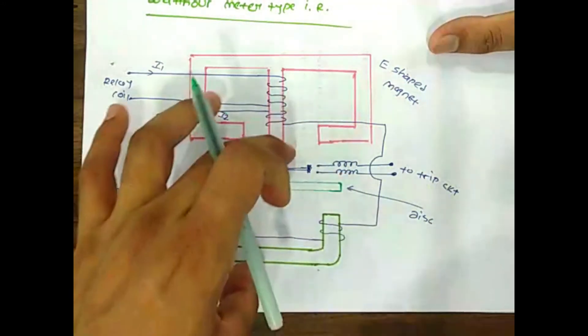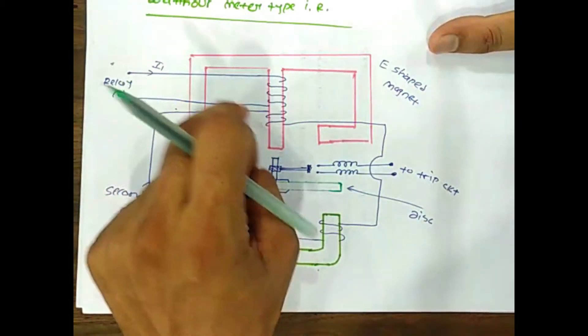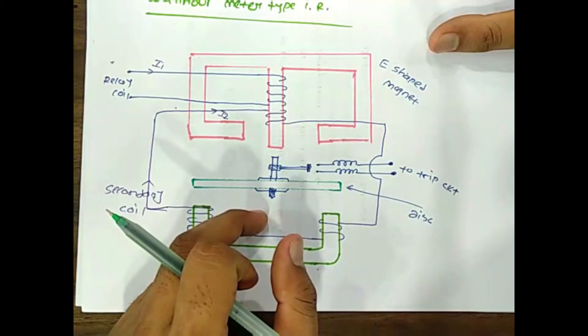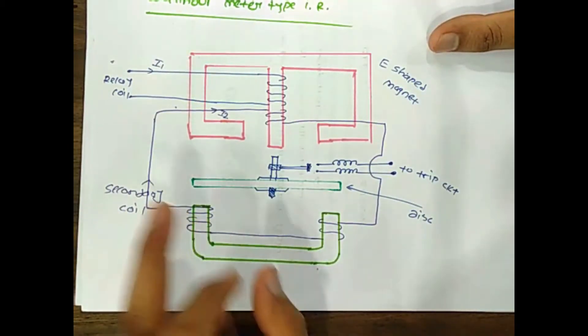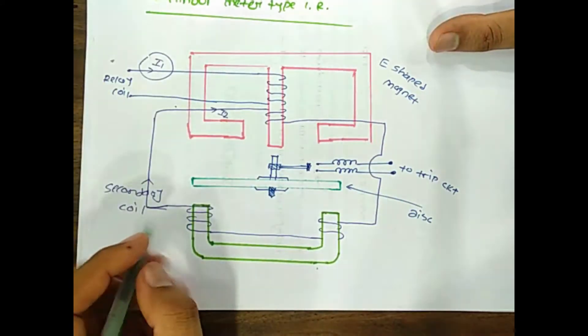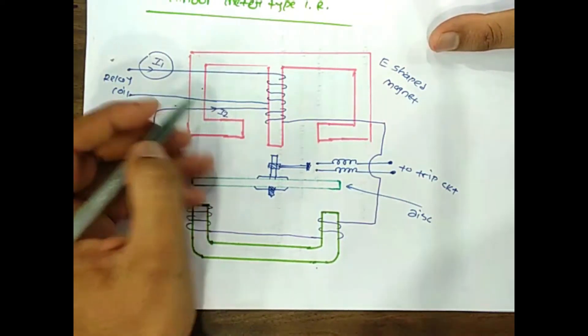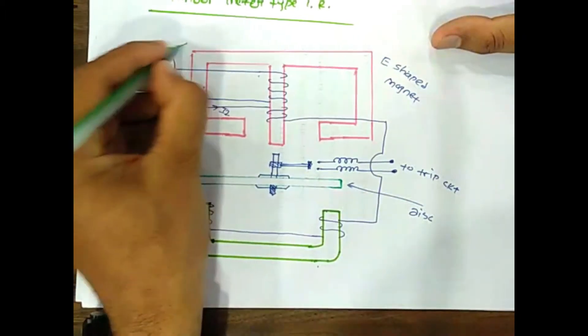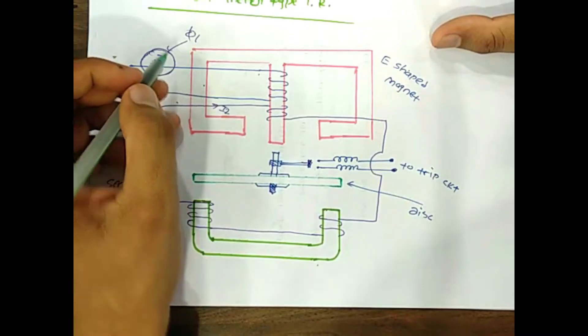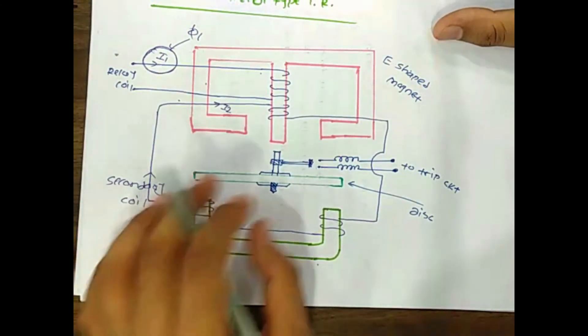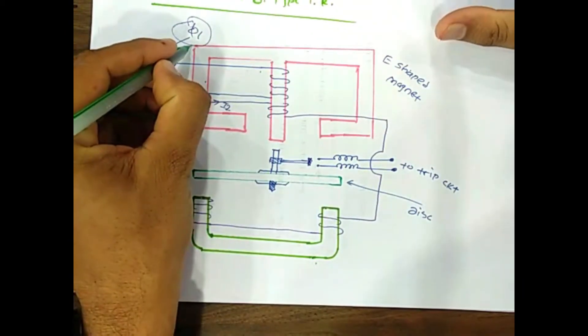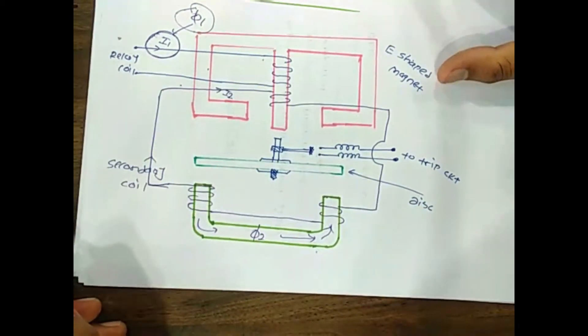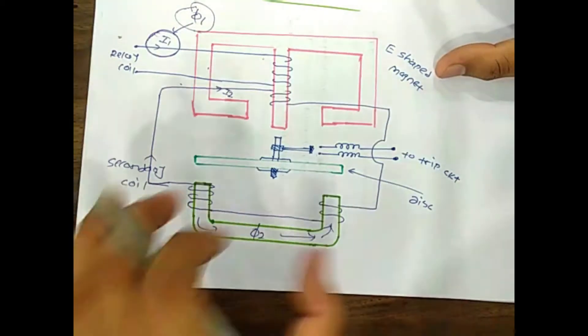The upper E-shaped magnet carries both the primary winding and secondary winding. The primary winding is the relay coil and the secondary winding is wound separately. The primary carries the relay current i1, which produces the flux phi1 in this particular magnet.